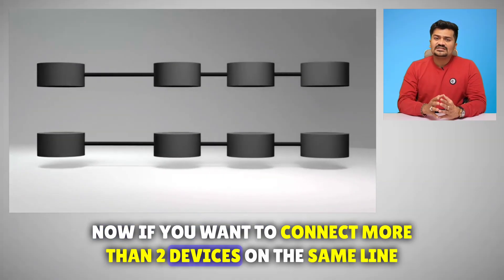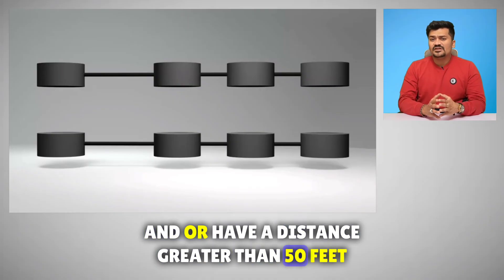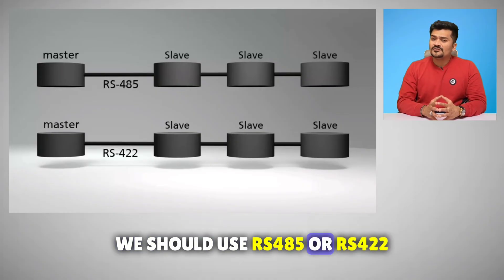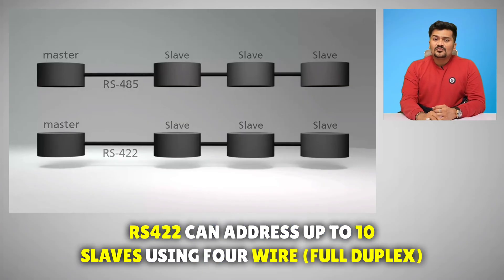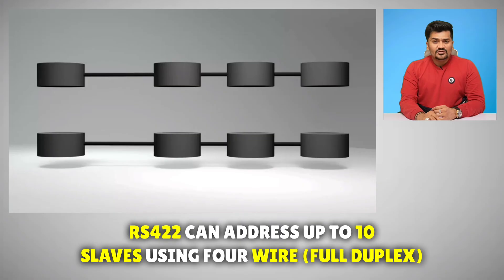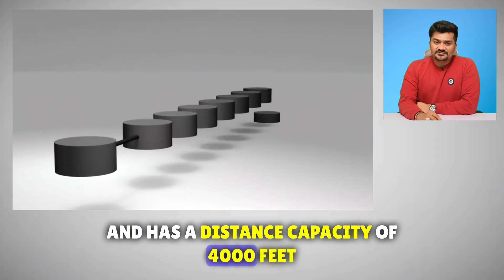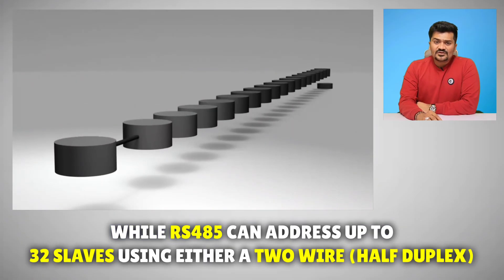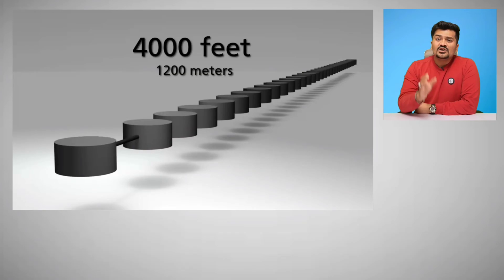If you want to connect more than two devices on the same line, or have a distance greater than 50 feet, you should use RS-485 or RS-422. RS-422 can address up to 10 slaves using four-wire full duplex and has a distance capacity of 4,000 feet, while RS-485 can address up to 32 slaves using either two-wire half duplex or four-wire full duplex.